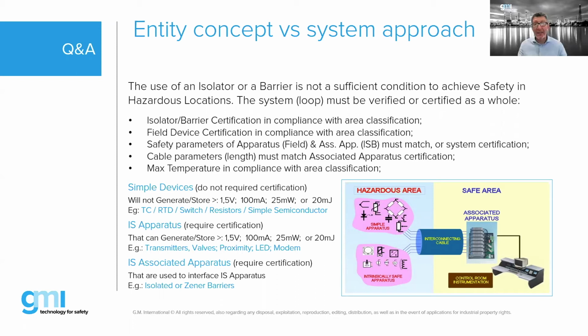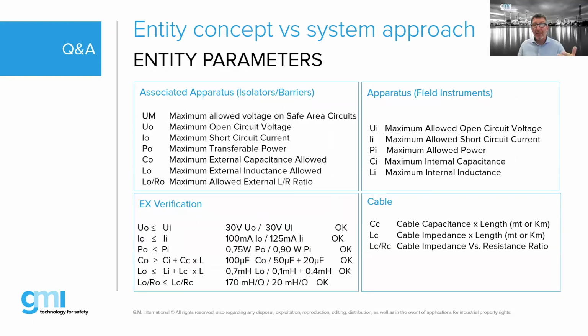In fact, the standard defines these numbers here: 1.5 volt, 100 milliamp, or 20 millijoule. I always remember that 20 millijoule is very, very little energy. Those simple devices don't require certification, but all other devices will require some kind of certification. Then you need to match the two certificates: the associated apparatus, so the barriers, and the field device.